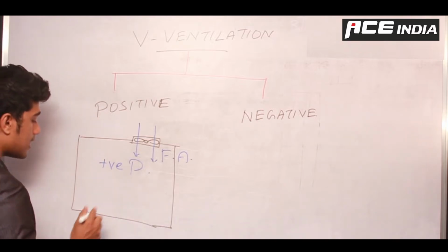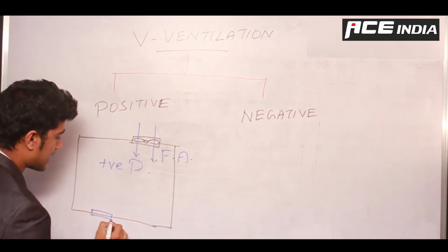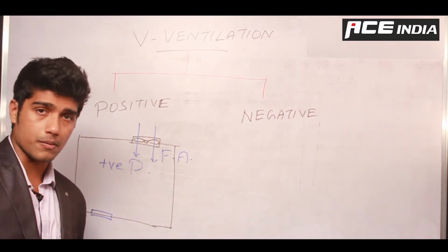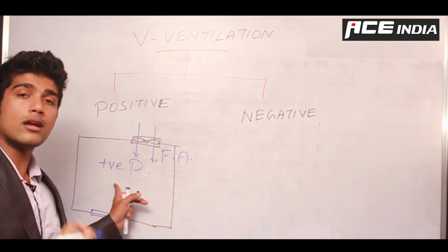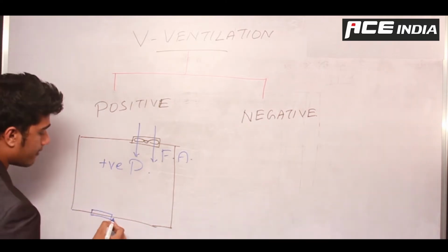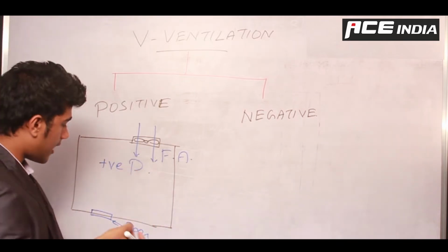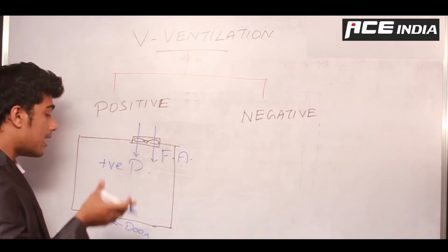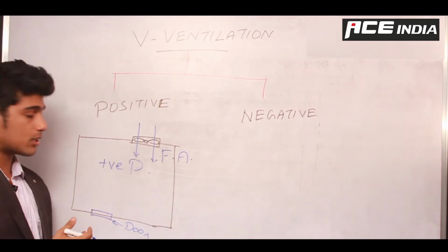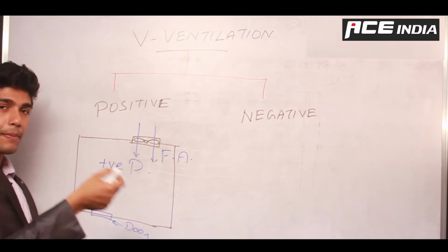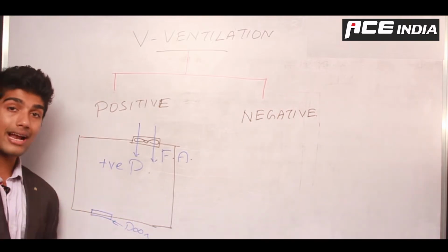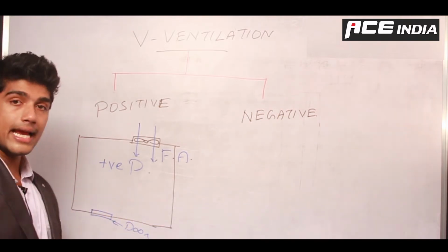Now what happens here is, if I continue pushing air inside, the pressure inside will be intolerable. So I need this pressure to be compensated. For this, say I have a door here. Normally in each door, if I have a proper ventilation system in the restroom or in any kind of situation, I have a small gap underneath the door which is known as a door undercut, or it can be termed as a bleed space.